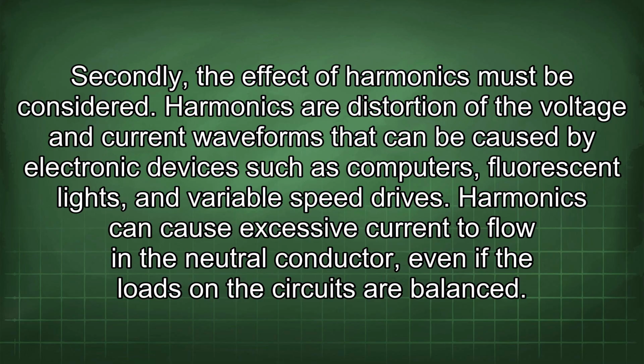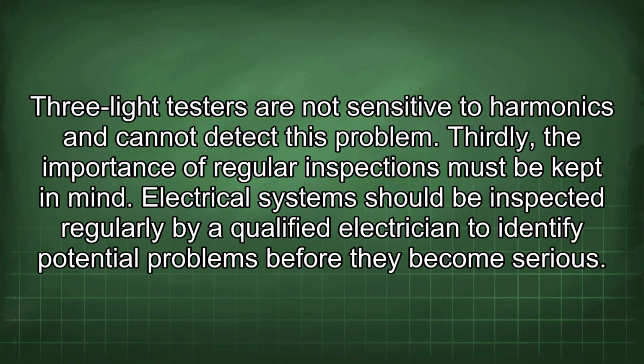Secondly, the effect of harmonics must be considered. Harmonics are distortion of the voltage and current waveforms that can be caused by electronic devices such as computers, fluorescent lights, and variable speed drives. Harmonics can cause excessive current to flow in the neutral conductor, even if the loads on the circuits are balanced. 3-light testers are not sensitive to harmonics and cannot detect this problem.